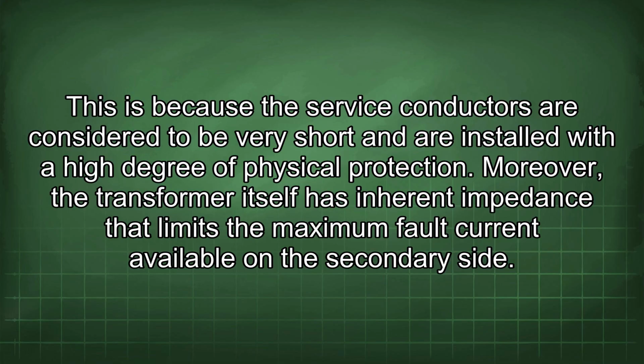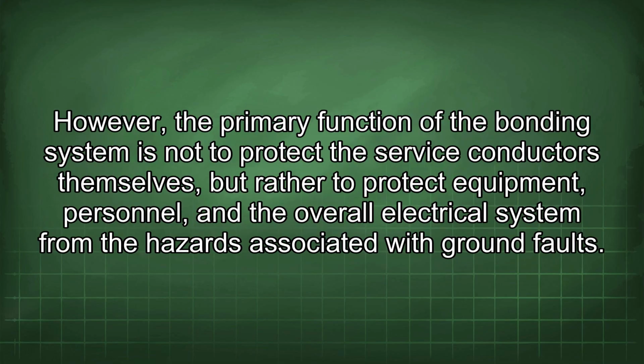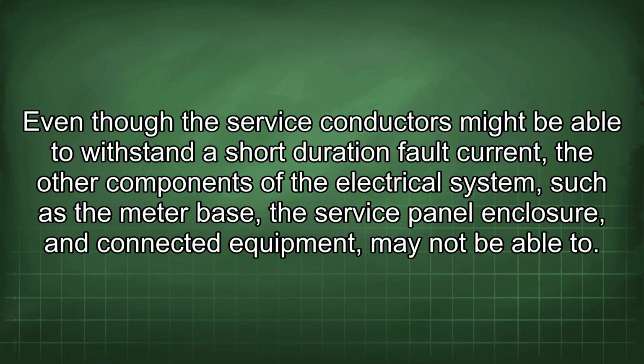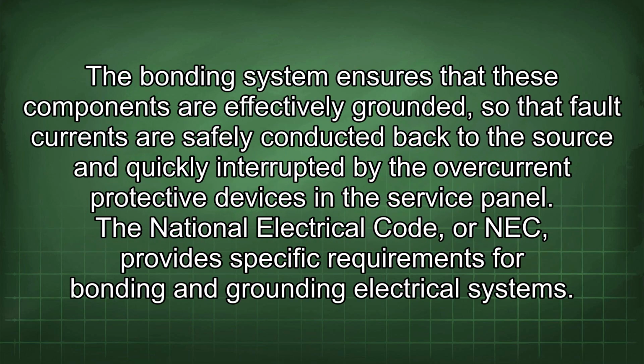Moreover, the transformer itself has inherent impedance that limits the maximum fault current available on the secondary side. However, the primary function of the bonding system is not to protect the service conductors themselves, but rather to protect equipment, personnel, and the overall electrical system from the hazards associated with ground faults. Even though the service conductors might be able to withstand a short-duration fault current, the other components of the electrical system, such as the meter base, the service panel enclosure, and connected equipment, may not be able to. The bonding system ensures that these components are effectively grounded, so that fault currents are safely conducted back to the source and quickly interrupted by the overcurrent protective devices in the service panel.